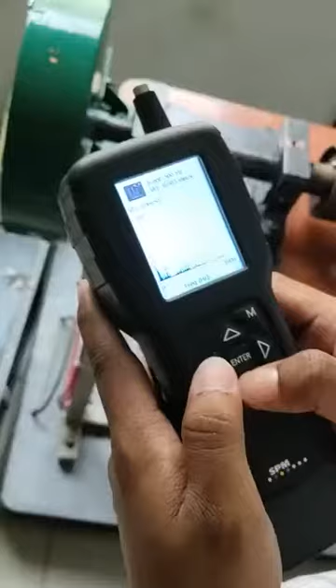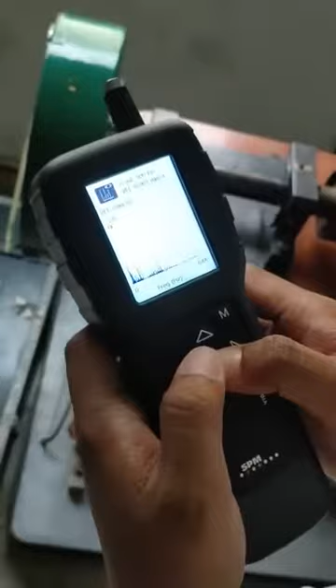For spectrum analysis, you have to provide the RPM here by pressing enter button. Right now this equipment is running with 1415 RPM. I am setting it. After setting this, you can see the 1x 2x peaks here. Here it is showing as 1x.